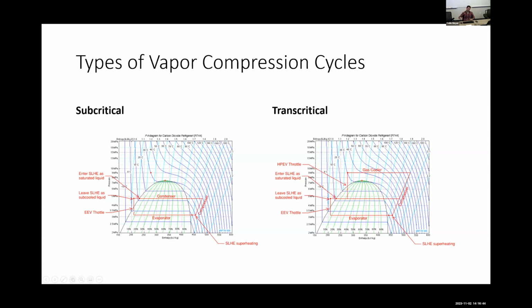That could be two or three stages. This is showing single stage. The key thing is that in the condenser, we're below the top of the dome. We're actually condensing saturated gas into saturated liquid, and there's no temperature change in that process.